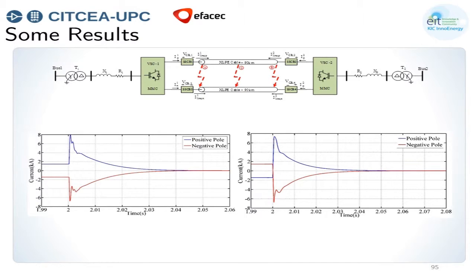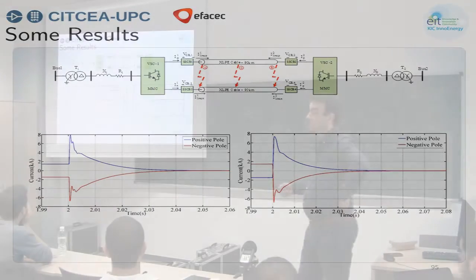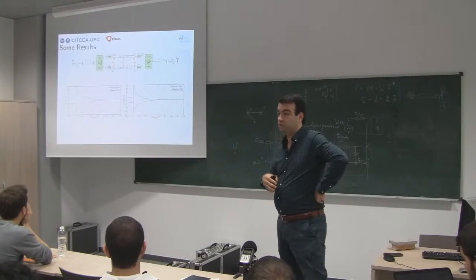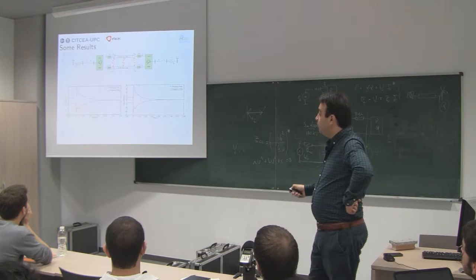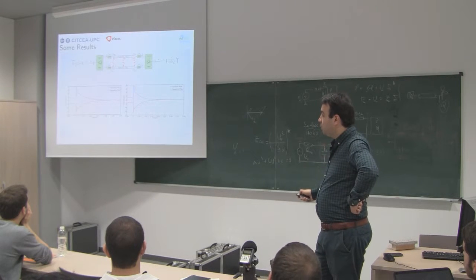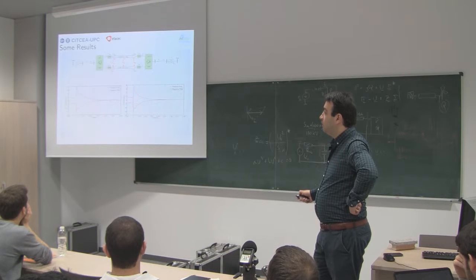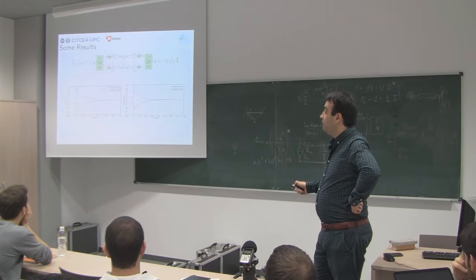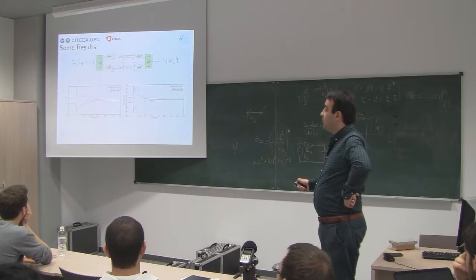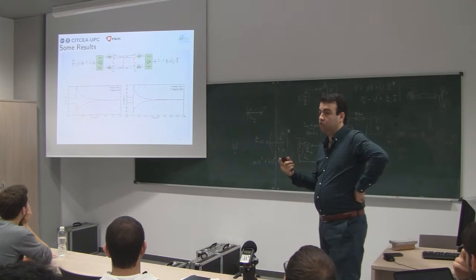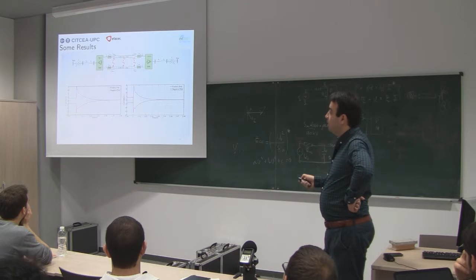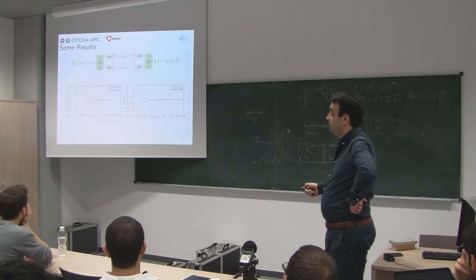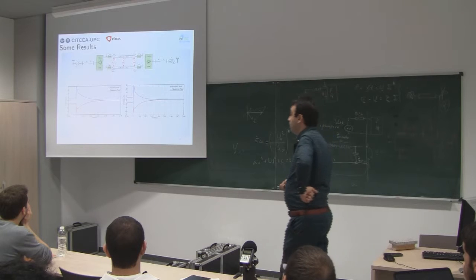And there is no problem. So here we can see these currents, which are the currents flowing through the cable. You can see the peak current in the cable is higher because we have the pre-charge capacitor, which is connected to the fault point, and the fault current is damped slowly in the cable.